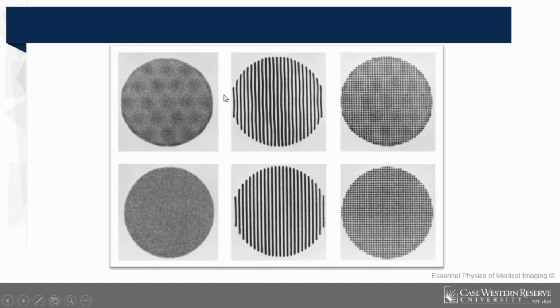These are blank scans, nothing in the field. It should be uniform like this, but they are not. So you need some corrections to make them uniform, but I did this intentionally just to show you where this array of photomultiplier tubes are put behind the crystal, and they have their finite size. They are not small. So how are you going to image? Let's say one gamma photon hits the crystal detector, right, it does scintillations, and the nearby PMT will get response signals.